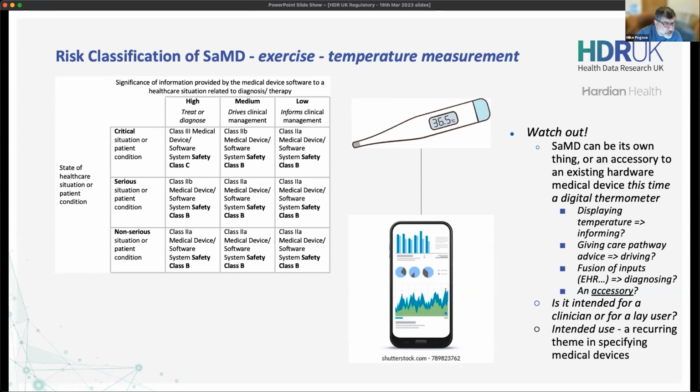So is it possible to certify rehabilitation systems, software, hardware using Rule 11? This is really difficult to understand. When people say Rule 11, for those who aren't aware, that is alluding to the European Union medical device regulation that basically says what this matrix is on the screen. So then we come back to the question, I'll reflect the question back. Are you treating with the rehabilitation system? The software part would be Rule 11. Is there really a hardware element? What's the hardware element? Is it an accessory to make the software work? Is it something different? So I hope that what I said before starts to cover that question.